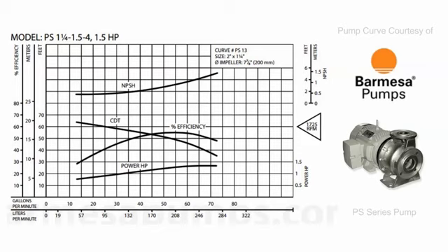Now, I really like this particular pump curve as an example because you can really see the detail of information that's offered in this little graph. This particular graph shows the motor speed, 1725 RPM. It shows horsepower requirements. You've got gallons per minute, liters per minute. You've got the efficiency represented here. You've got the head in meters and feet. And this particular pump is offered in 1 1/2 horsepower, because then it's able to achieve the full range of the curve without any fear of overloading.